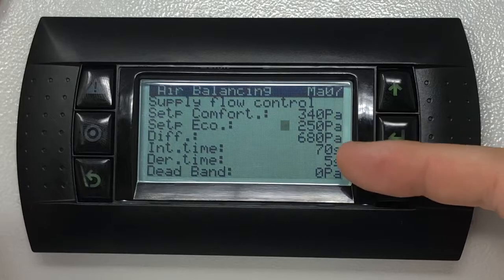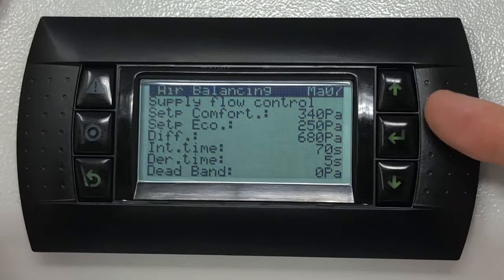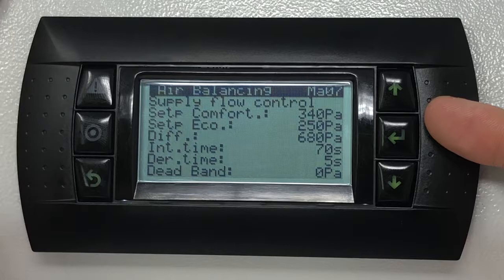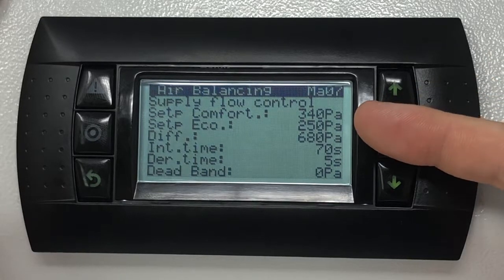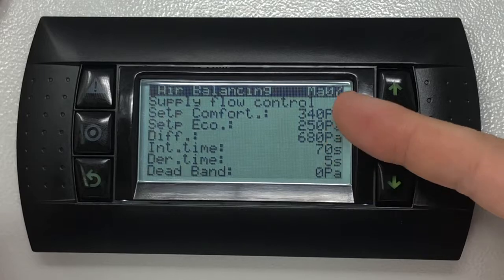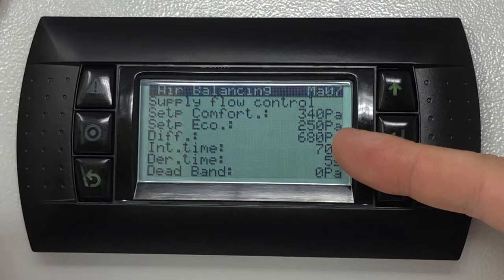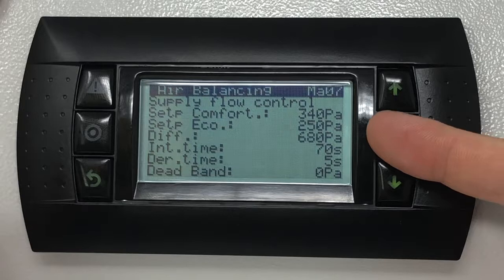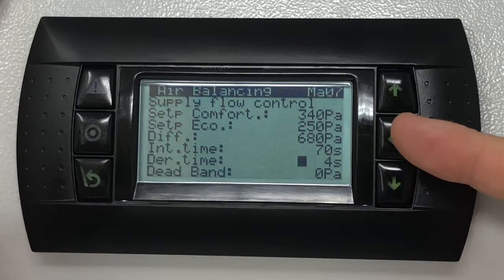The differential, integral time, derivative time, and dead band are parameters that will have to be adjusted to tune the fan speed regulation to suit the possible fluctuations and hunting of the fans. As a general guideline, we recommend inserting a differential which is twice the value of the set point, an integral time of about 70 seconds, a derivative of 4 seconds, and a dead band of 0.